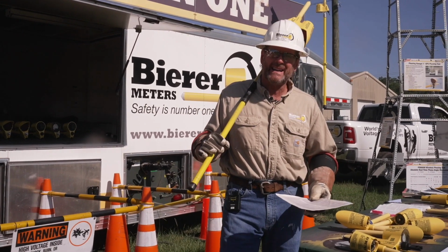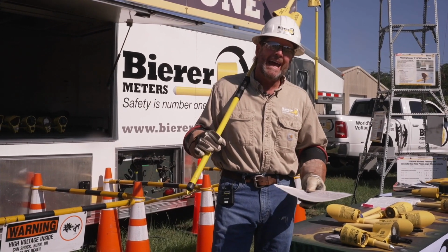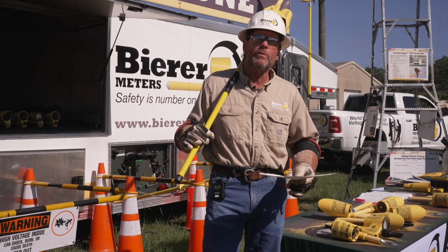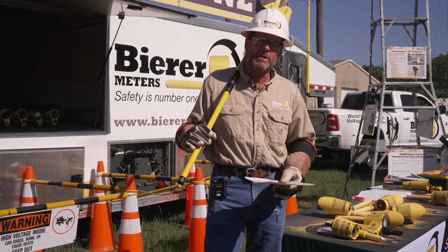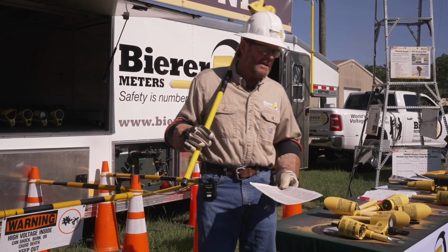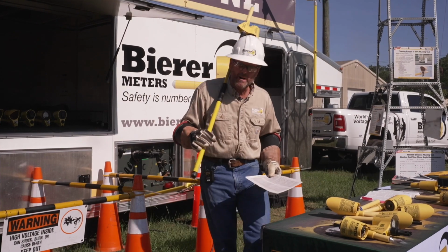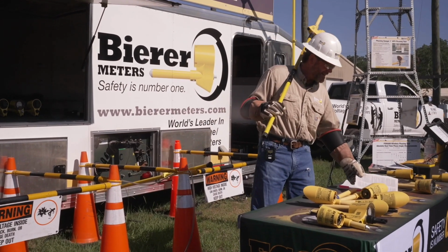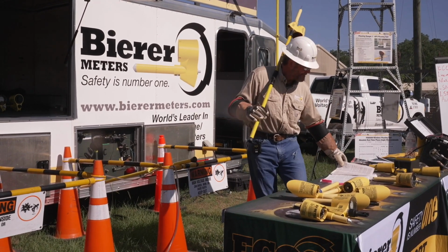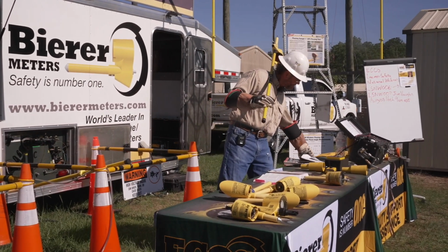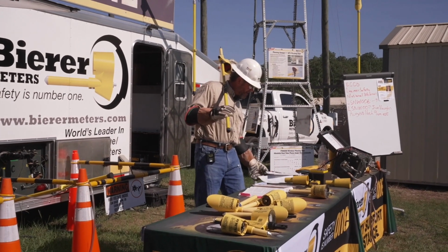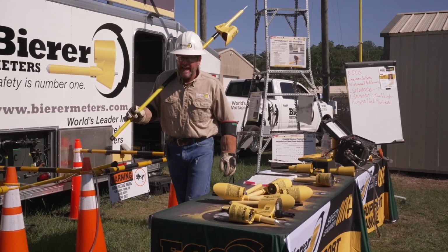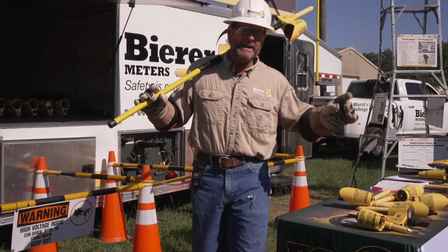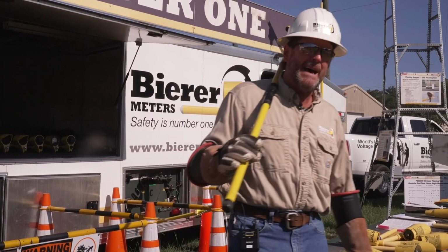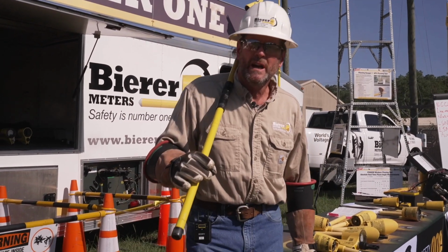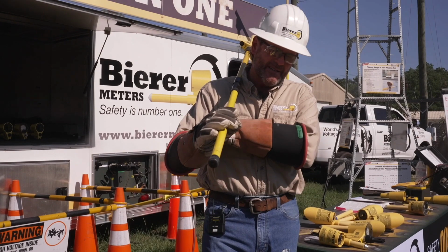If we have an absence of nominal voltage and induction, and we don't want to see any backfeed, that's what our tools will tell us. If you're using a non-contact tool on an underbuild or in a substation, you're going to have a lot of influences, and those will affect the non-contact tools. You'll get readings two feet away and not know for sure if there's an absence of nominal voltage, backfeed, or induction.